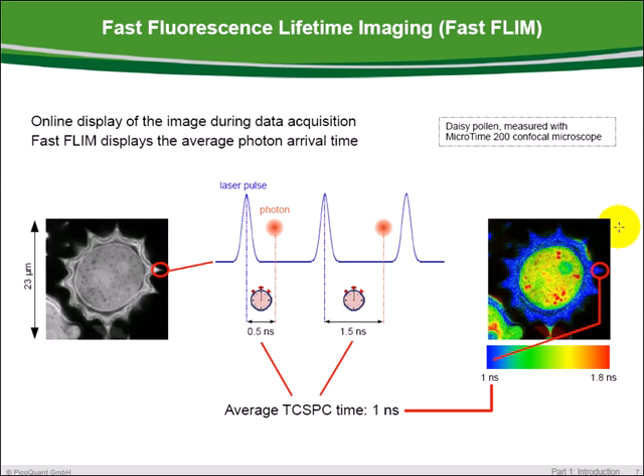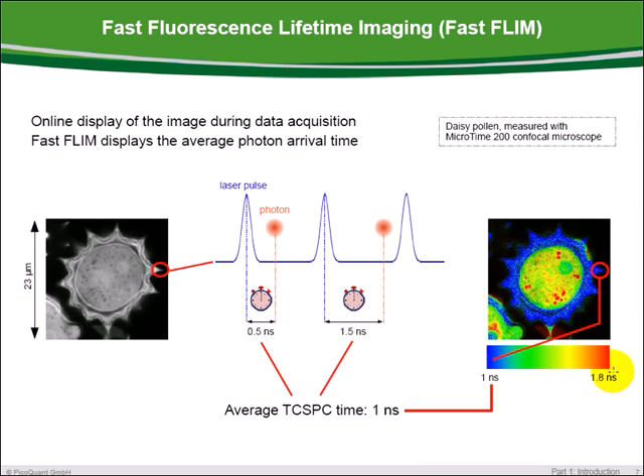Using the fast FLIM technique, the lifetime image is already displayed during data acquisition. For every pixel in the image, we calculate the start-stop times between the laser pulse and the arrival of the fluorescence photon — in this case 0.5 nanoseconds and 1.5 nanoseconds. The average lifetime, in this case 1 nanosecond, is displayed using a rainbow color scale from blue to red. This process is performed for each pixel, resulting in a FLIM image displaying the average lifetimes of the sample.